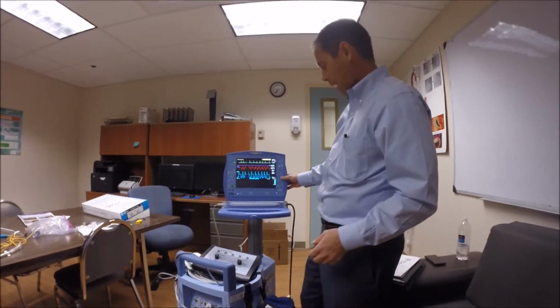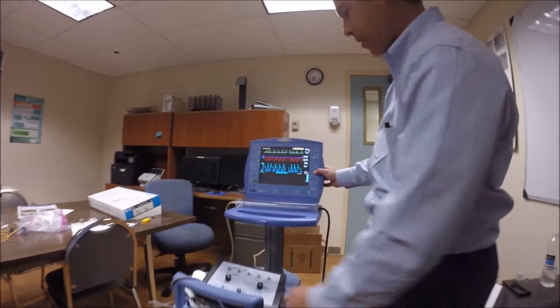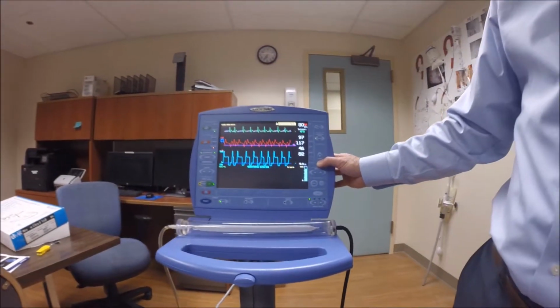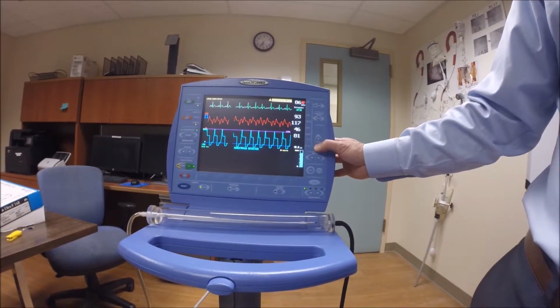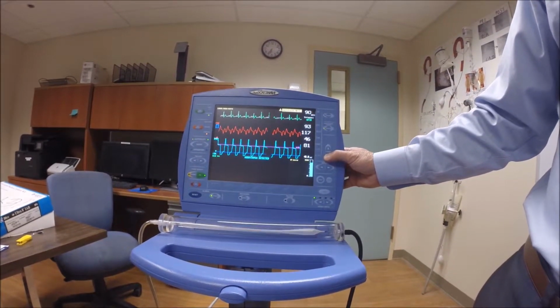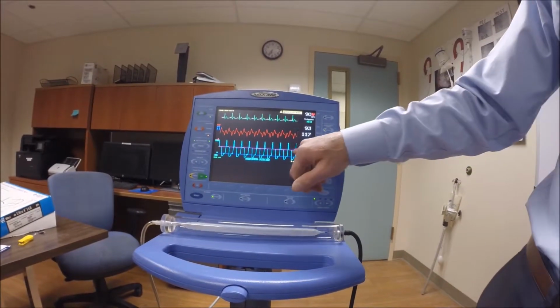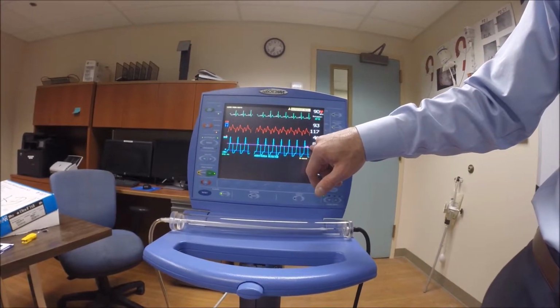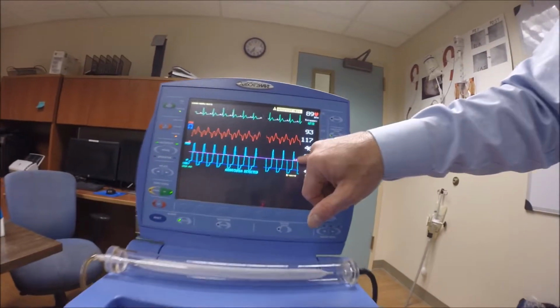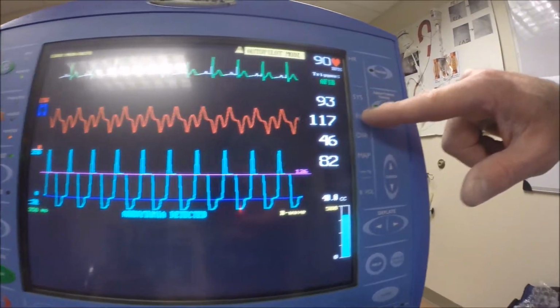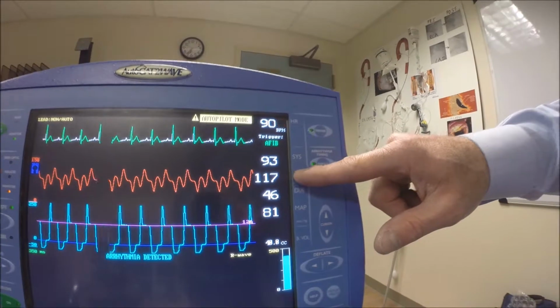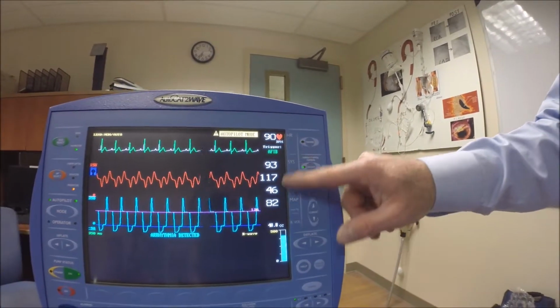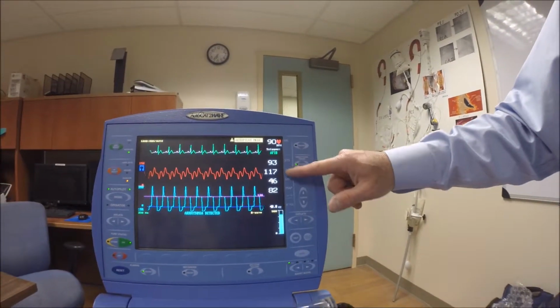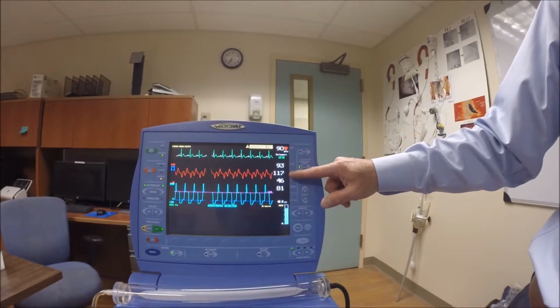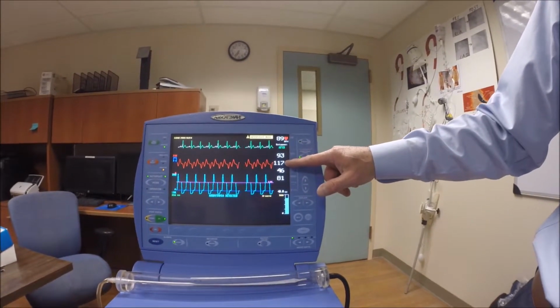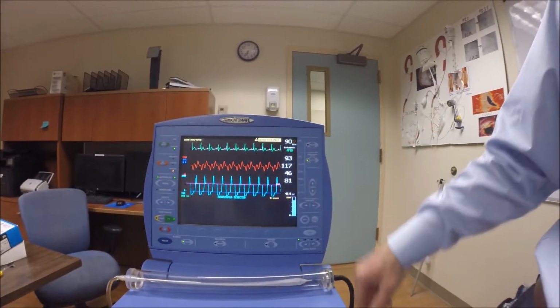To do that, I bring my cursor down and I drop it onto this balloon pressure waveform, onto the chair of that balloon pressure waveform right here, and I get a corresponding pressure reading of 126. I want that number to be as close as possible to my patient's augmentation pressure. 126 and 117, those are pretty close. I actually have a range I can work within, 25 above and 25 below my augmentation. So right now I'm within that range.